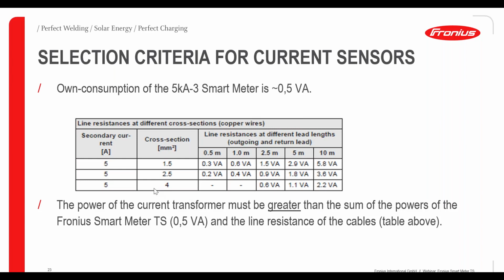For example, if you have a cable between the smart meter and the current transformers, with a cross section of 2.5 square millimeters and a length of 5 meters, then we have a line resistance of 1.8 volt ampere. So this value added to this value should be the minimum required when choosing the correct current transformer. Of course, this is the minimum required, but the higher the better. So this is how we choose the correct current transformers when installing that commercial Fronius smart meter.